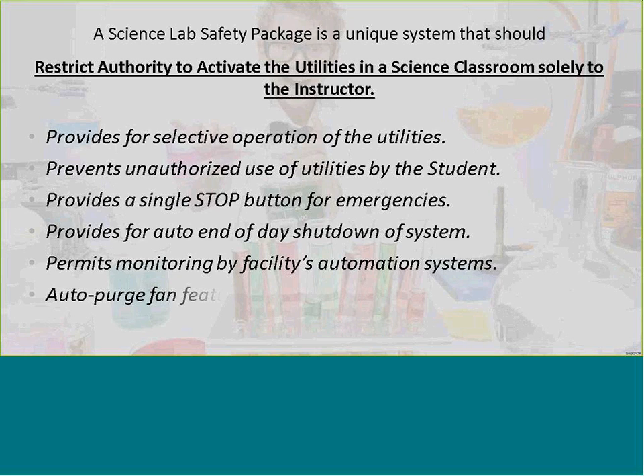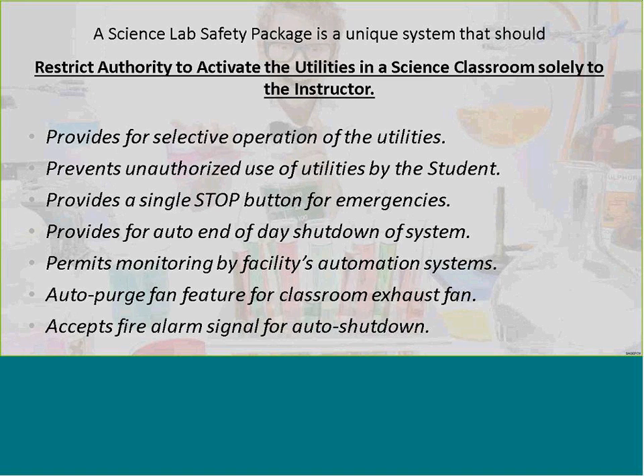We just talked about automation there. Now, a lot of times you need to also control the fan, an exhaust fan in a classroom. And in a classroom, you have purge fans that will come on when an experiment has gone awry, where you've got a chemical spill and you're trying to get it out of the room. The panic button will enable an exhaust fan to come on and purge any chemicals or anything in that classroom at that time out. The exhaust fan is controlled by a switch or by the panic button, but if an alarm signal is received, then the purge fan is not active because we don't want to introduce more air into a fire area. So alarm will disable, panic button will enable.